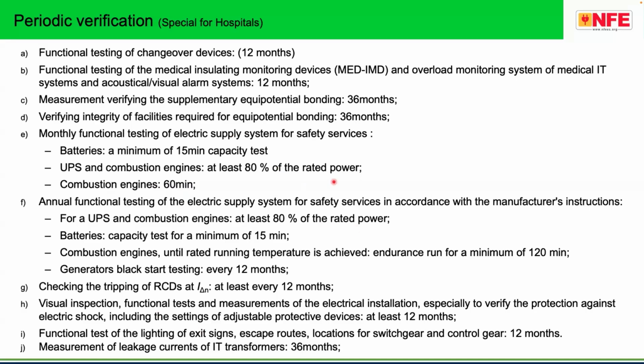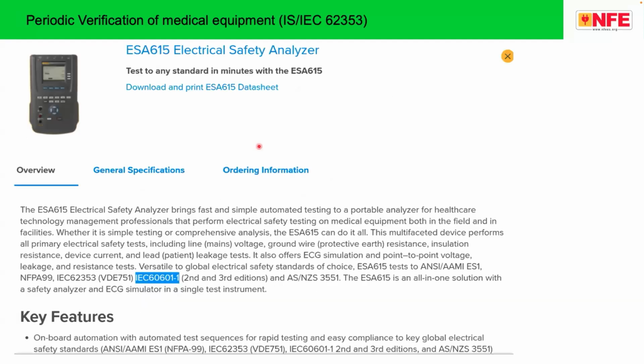So these additional safety measures, if you do them periodically, you are sure that the changeover switch is in good condition, so that in an emergency you are not under risk. The backup electrical supply sources such as UPS and the DGs are in good condition. They are efficient. They are ready to cold start. They are ready to work for whatever time is required. So all these periodically you must ensure.